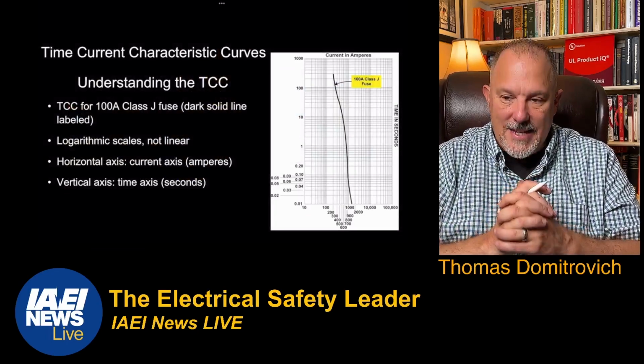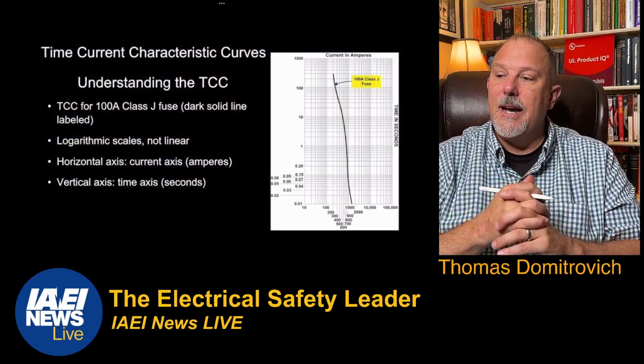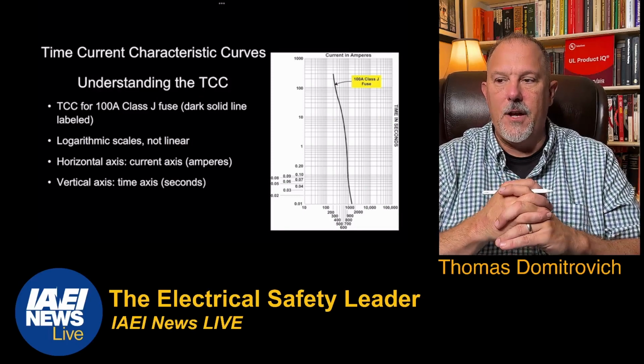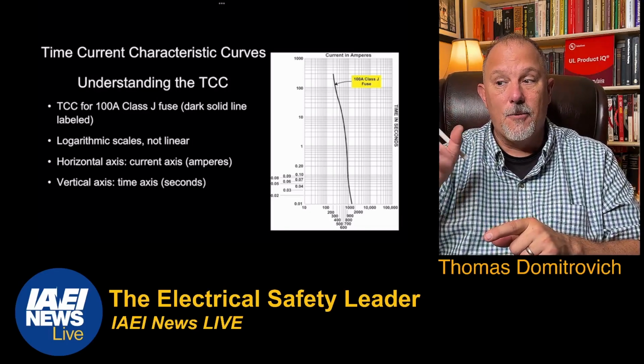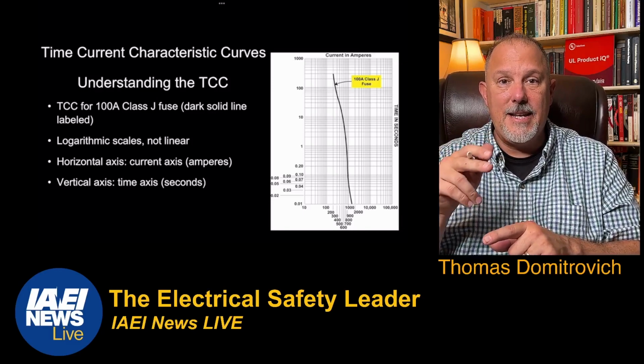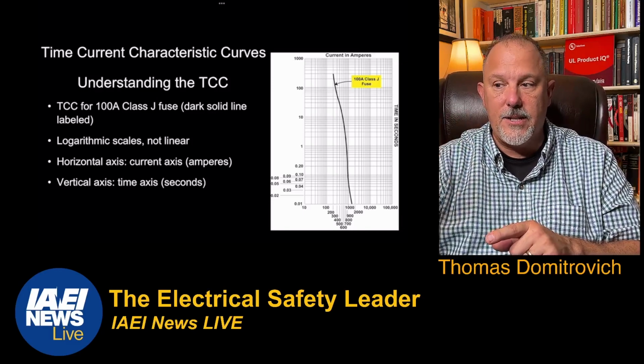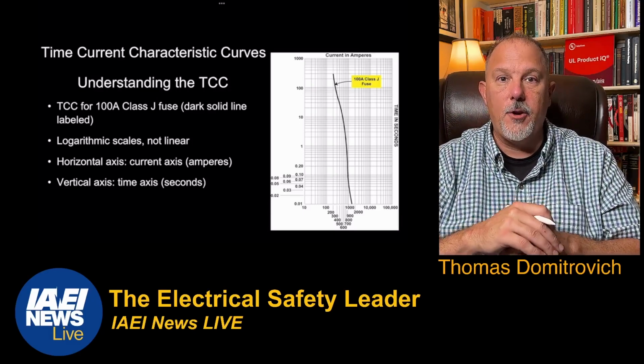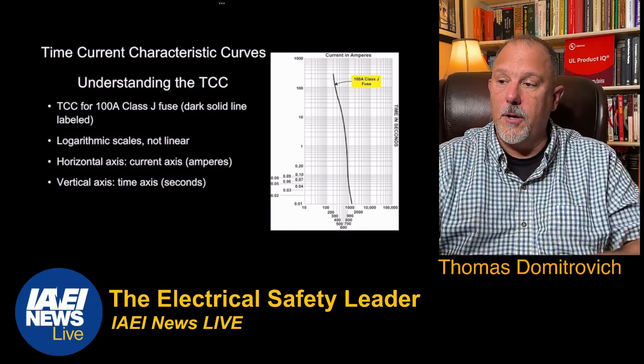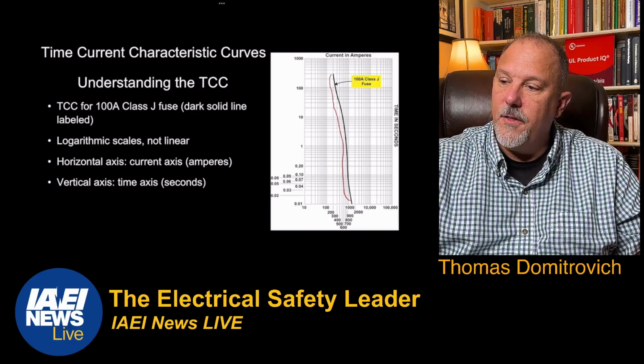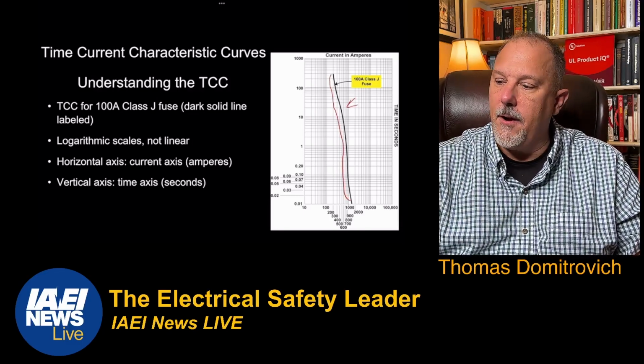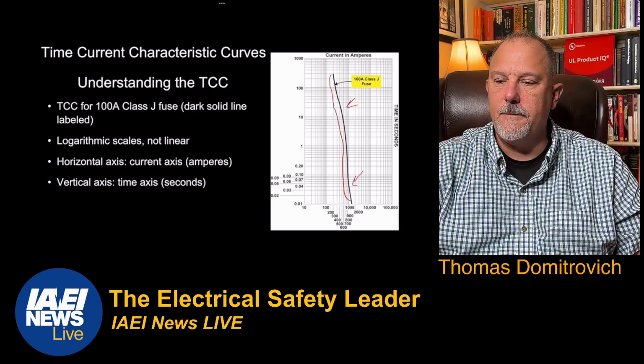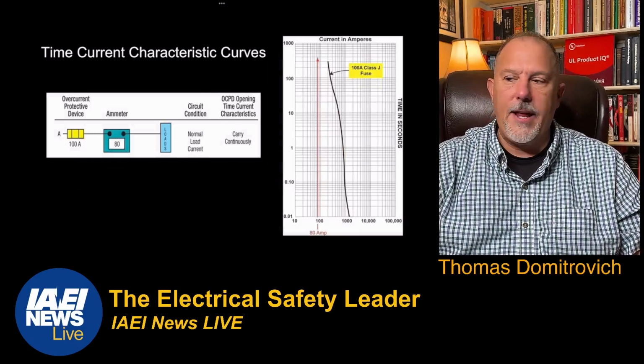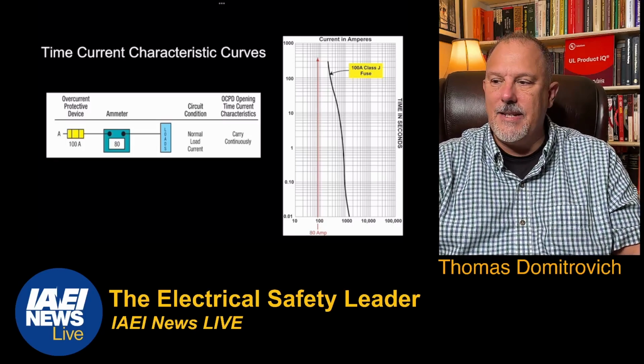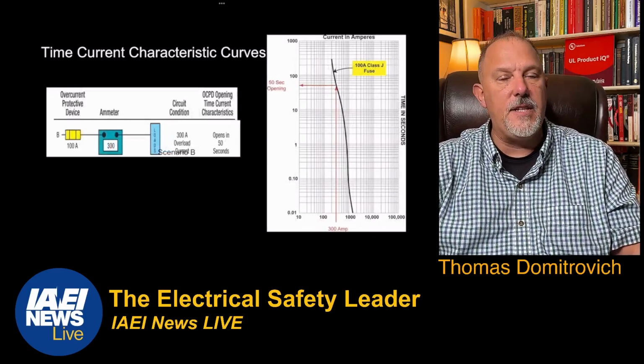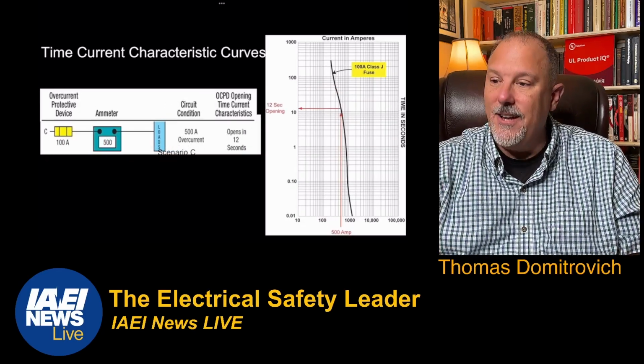Now, let's think about a time current characteristic curve. The amount of time that I let current flow will be dependent upon the clearing time, or the time current characteristic curve, TCC curve. It's not time current curve, it's time current characteristic. Characteristic is a very important part. This is a characteristic of the curve. The fact that it has a little bit of a swing up there and a little bit of swing in there, that's the characteristic. So if I take a look at this 100 amps Class J fuse, I could let 80 amps flow through it continuously. If I put 300 amps, it will clear in about 50 seconds. If I put 500 amps, it'll clear faster at 12 seconds.